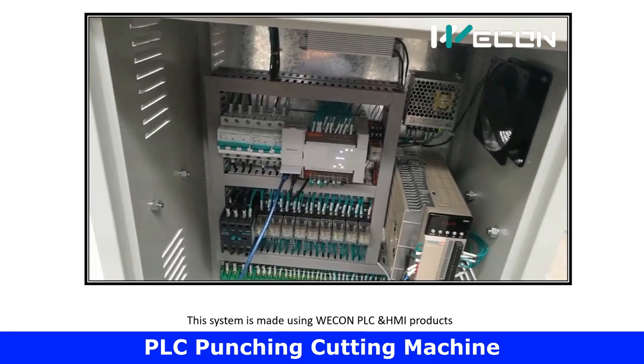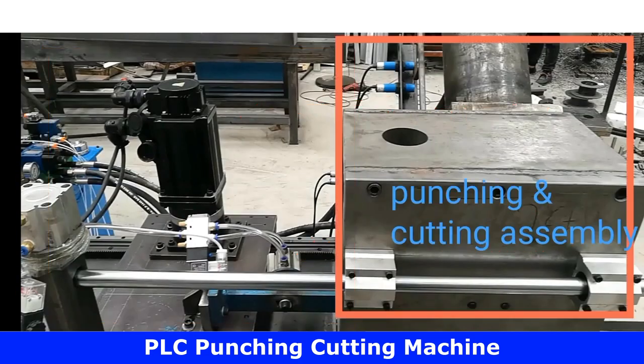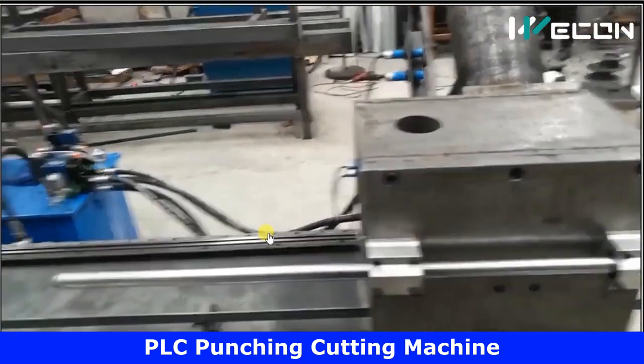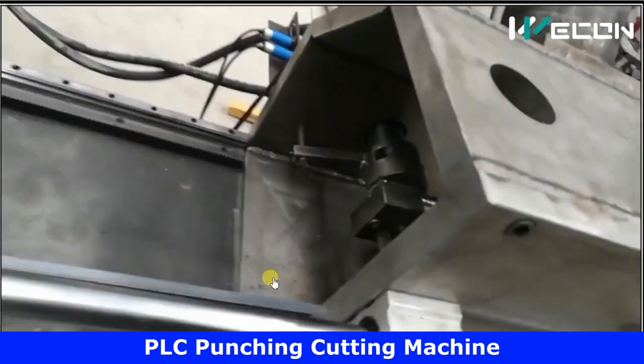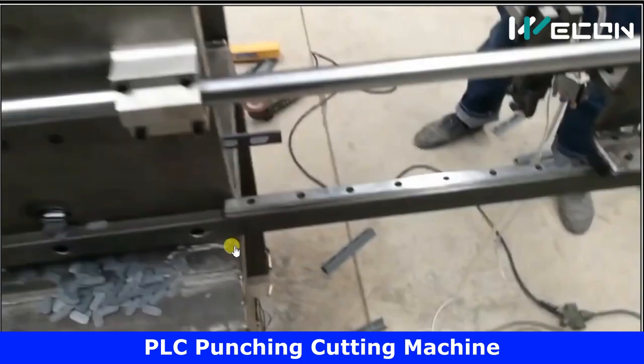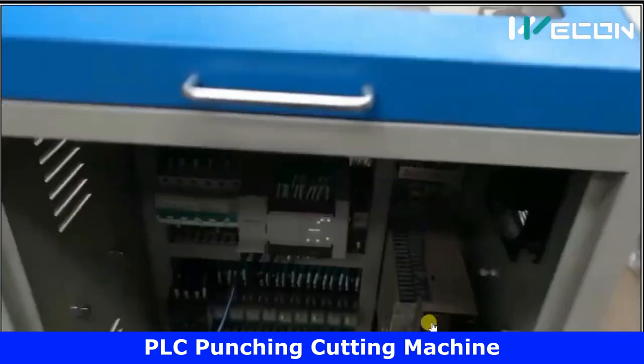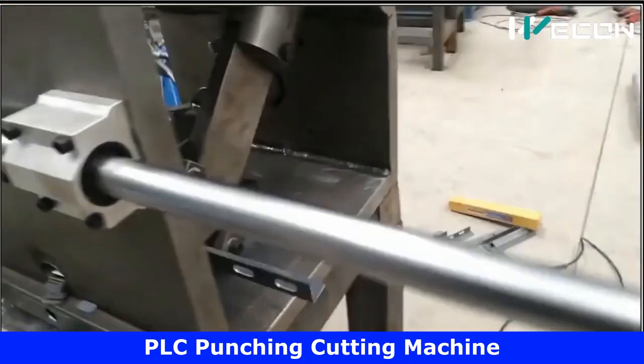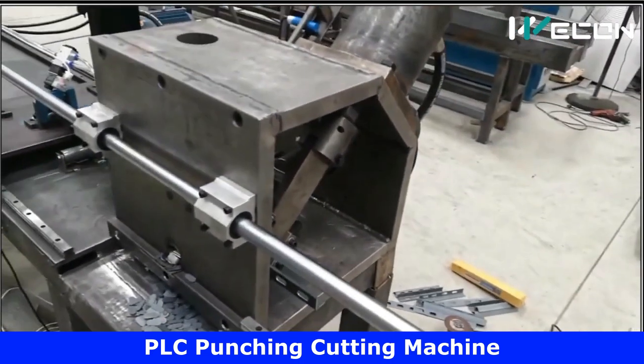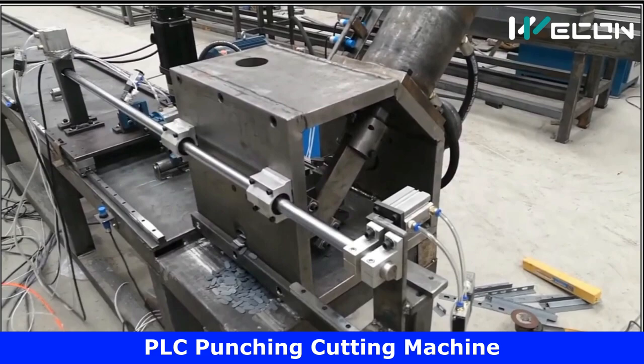This whole system is built using WECON PLC and HMI products. Through the HMI screen we can select the number of punches in the plate, the distance between punches, and the overall length of plate to produce. Let us see the complete machine working at actual speed — this is the real application. You can see punching and cutting cylinders operating, the motor moving in steps, and the finished product with its punches and cuts. The reason for making such videos is to help you build logic for real-time applications so you can create your own programs.